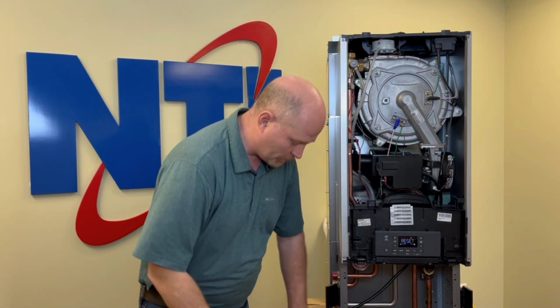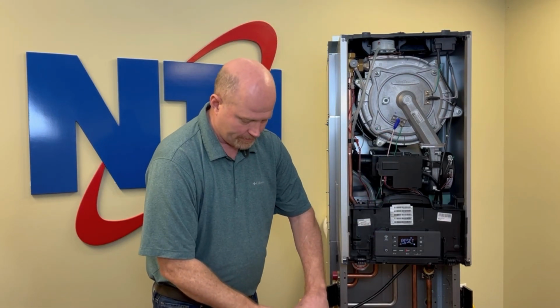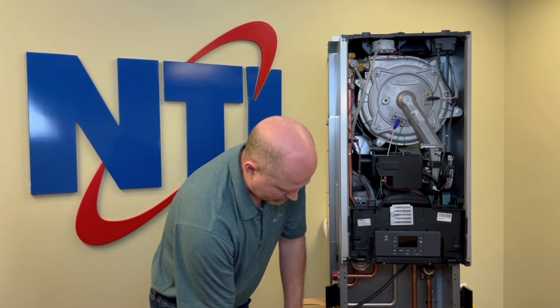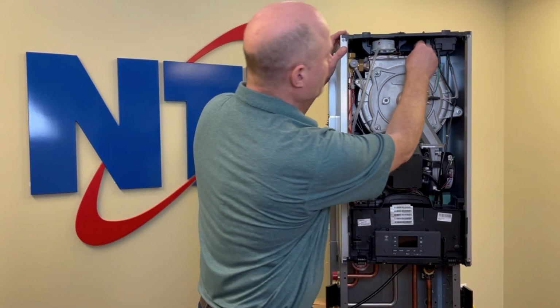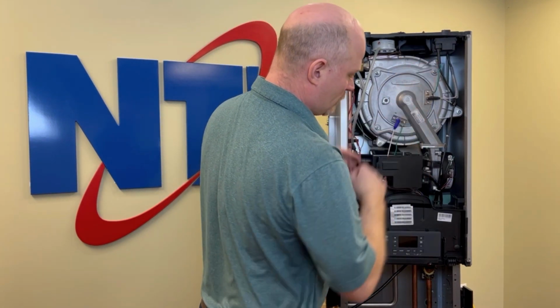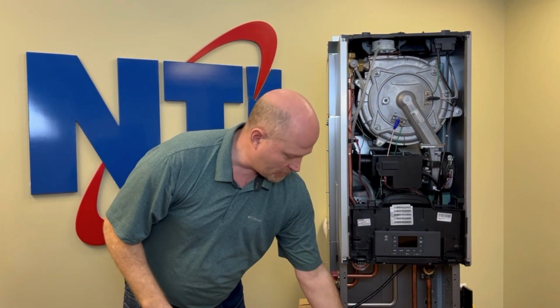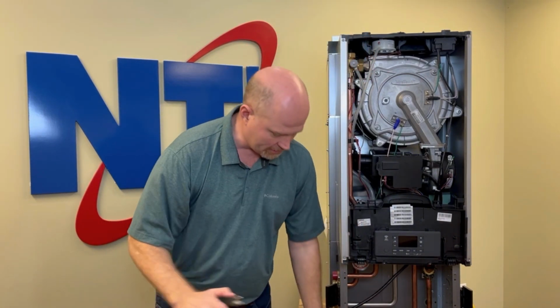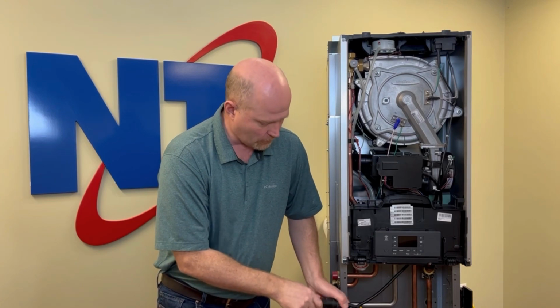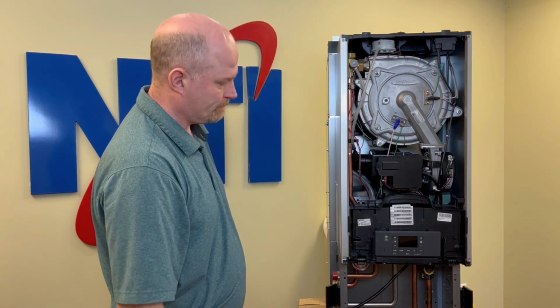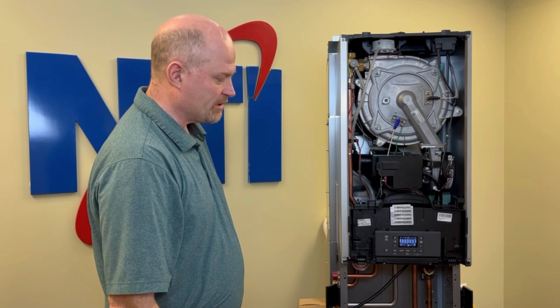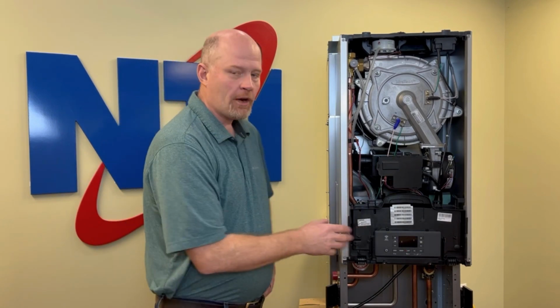Once the boiler has dropped below 149 Fahrenheit, you can disconnect power. I'm going to repair my sensor by removing the component that I was using to cause it to go into an error code. We're going to turn the power back on. And once the boiler boots back up, I can now reset this error.